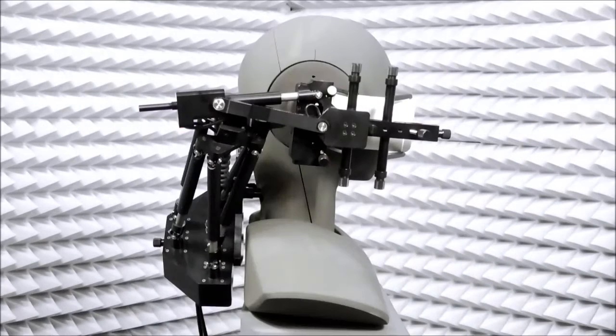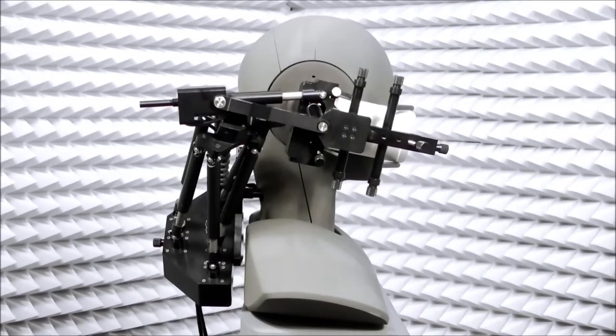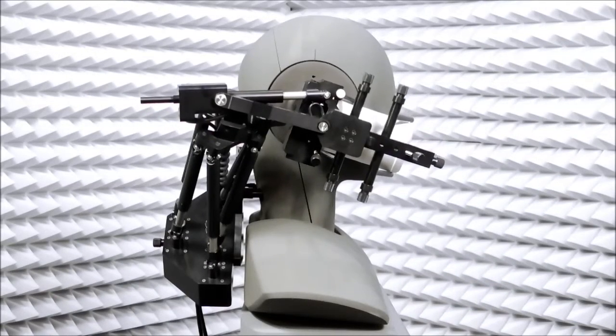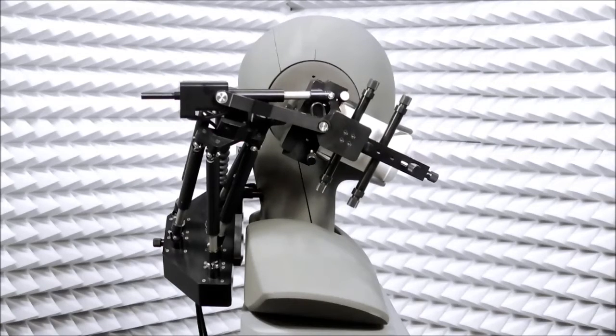HHP4 automatically places a clamped-in handset in a wide range of positions allowing, for example, positional robustness testing.